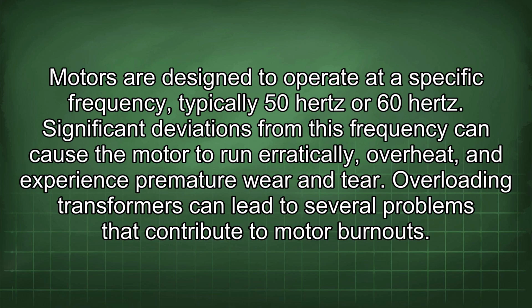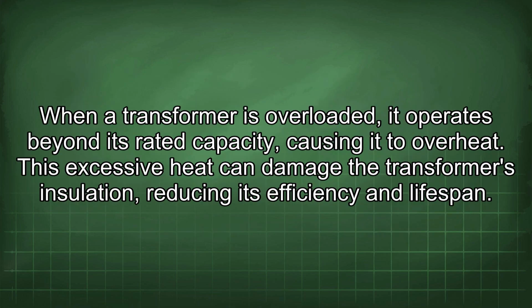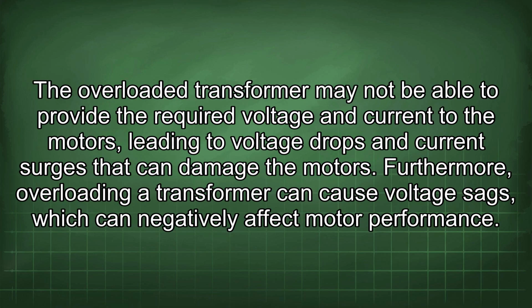Overloading transformers can lead to several problems that contribute to motor burnouts. When a transformer is overloaded, it operates beyond its rated capacity, causing it to overheat. This excessive heat can damage the transformer's insulation, reducing its efficiency and lifespan. The overloaded transformer may not be able to provide the required voltage and current to the motors, leading to voltage drops and current surges that can damage the motors.